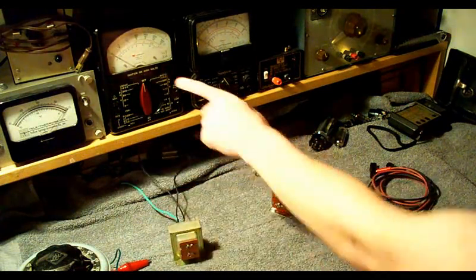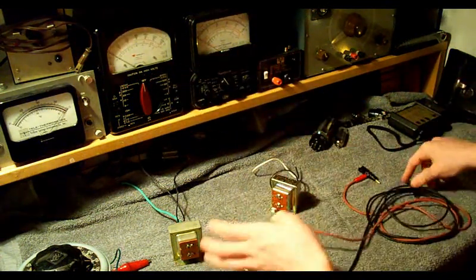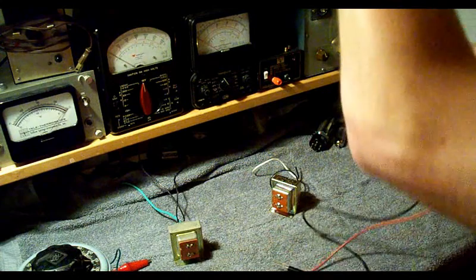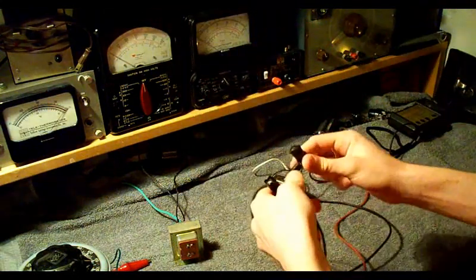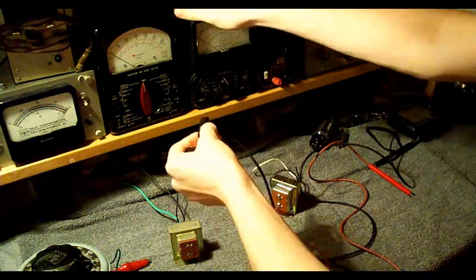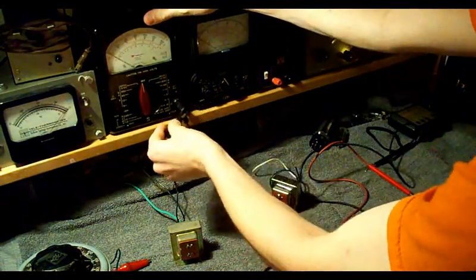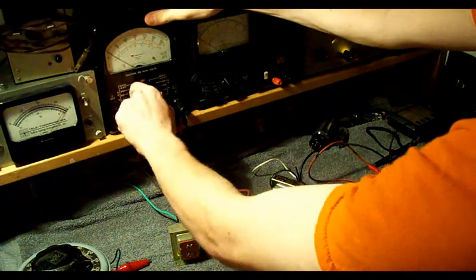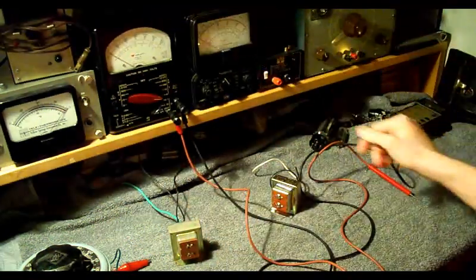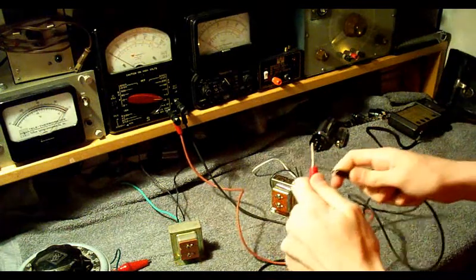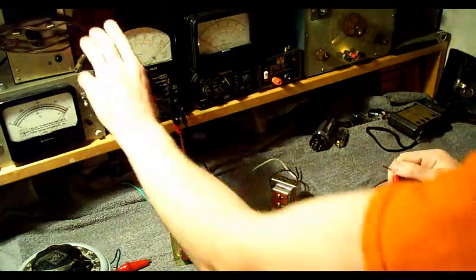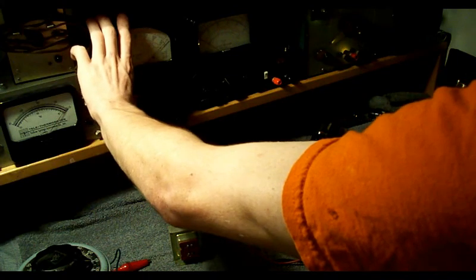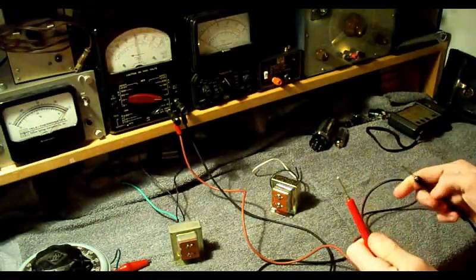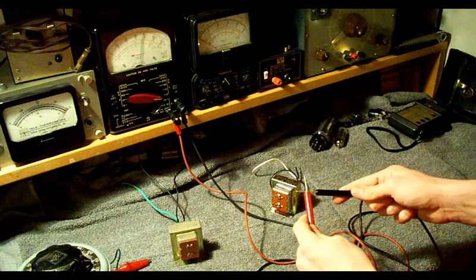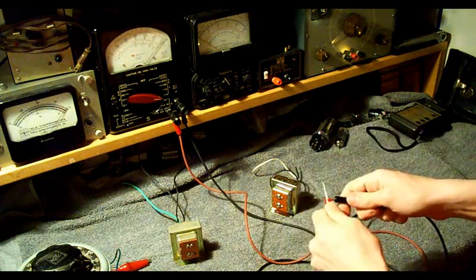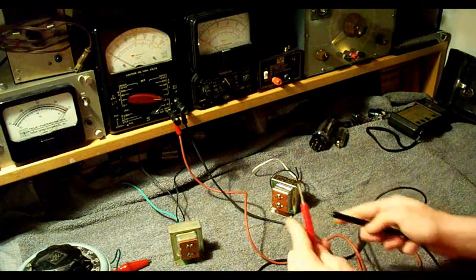So I'm going to be using my Triplett 630 here to test these transformers today. So I'm going to go ahead and get my test leads ready to go, and I'm going to set up the 630 to measure resistance. Hook up my leads. And then we're going to set it on the ×1 resistance scale. So when we short the two leads together, we should get full scale deflection. And we do. We'll adjust that so it's not pegging the scale. There we go. So we read 0 ohms when we short the leads together. Now that's what we should see right there, 0 ohms is a short.